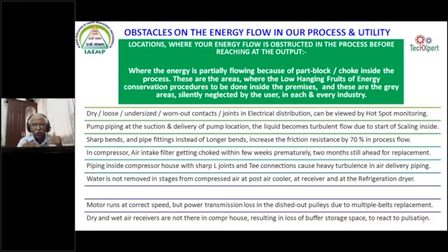Then the piping in the compressor house. Once the compressor house piping has all the T connections removed and made into conjoining joints, where a 45 degree slope of joints is given to the piping, definitely the turbulence on each and every T connection will disappear, and automatically the pulsations in the compressed air loading and unloading, that kilowatt zigzag fluctuations, will also go out, and automatically you can see the savings. In some of the industries we have seen almost up to around 8% of savings is possible because of this piping rearrangement.